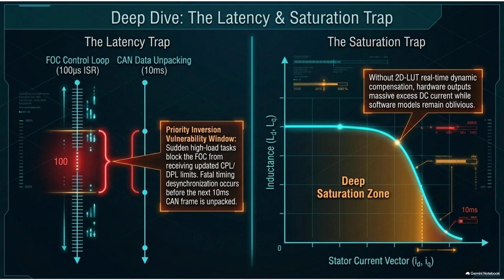And the motor controller, which is running at its blistering 100 microsecond loop, just keeps executing commands based on the stale limits. Right, entirely ignoring the slower bottleneck warnings from the BMS. Because it hasn't read the new email, basically. Pretty much, yeah. Okay, so we've established that the software can get bottlenecked and electromagnetic shockwaves can corrupt the data. But what happens when the hardware itself is actually lying to the software? Oh yeah, this is the physical wear aspect.